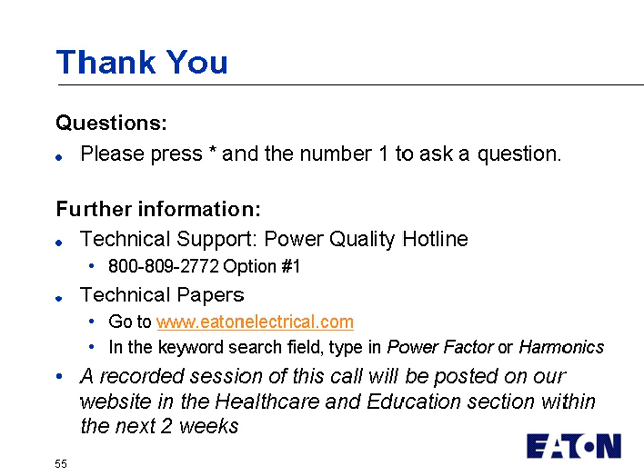What I found was an old Westinghouse document. It's kind of interesting. Back in 1979, they put together a list of all the utility companies around the U.S. For each utility company in, say, Pennsylvania, they listed how the power factor penalty may be applied and what type of power factor penalty it might be. Does it adjust the demand? Does it adjust the kilowatt hours, for example?